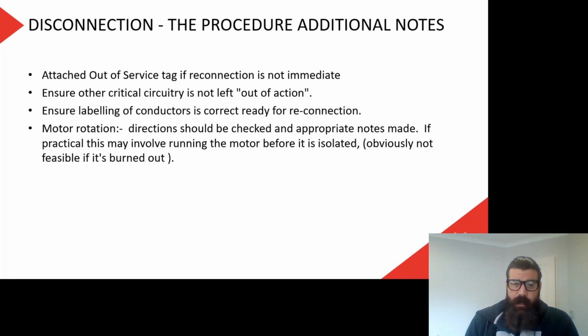We should attach an out of service tag if reconnection is not immediate. So if I'm not finishing the job that day, we must have an out of service tag. Ensure other critical circuitry is not left out of action. So if I've disconnected something and I'm removing it and there's other things on that same circuit, I'm going to need to make sure that what I've done is insulated, and I've got to turn the power back on for that circuit because there could be other things on there.